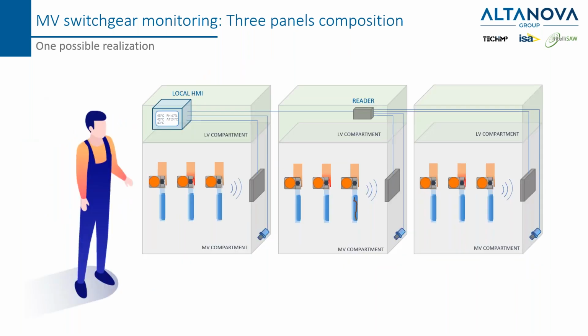One possible realization, a layout of the system, is to have, for example, these 3 medium voltage switchgear on a line. In the typical installation, you can notice all the wireless sensors inside the medium voltage compartment, the antenna, and the temperature and humidity sensor at the bottom of the medium voltage compartment. The reader is located in another panel rather than the local HMI, and then all is connected together.